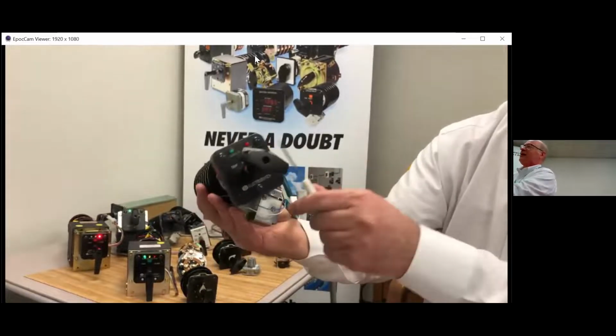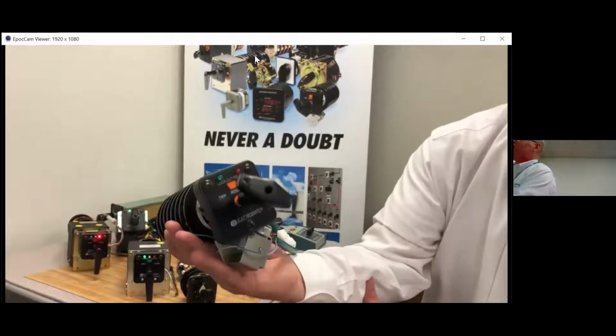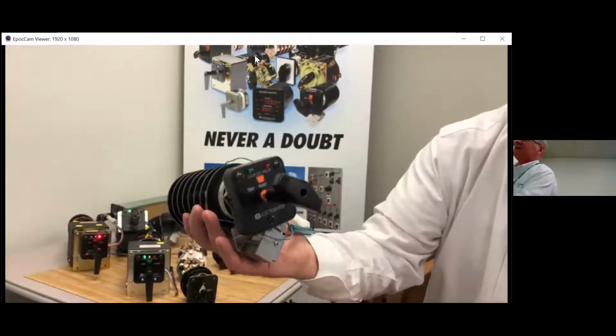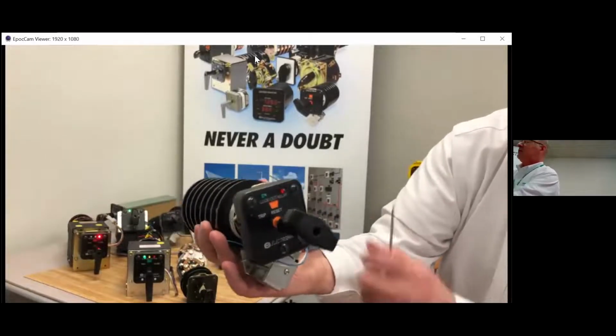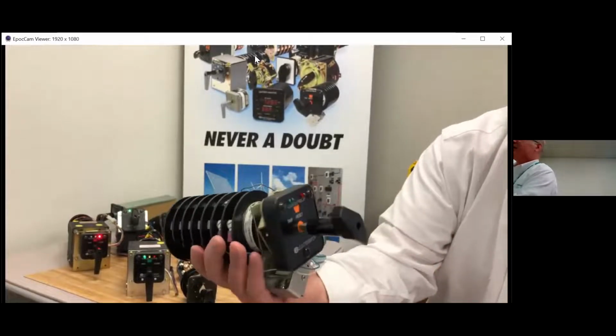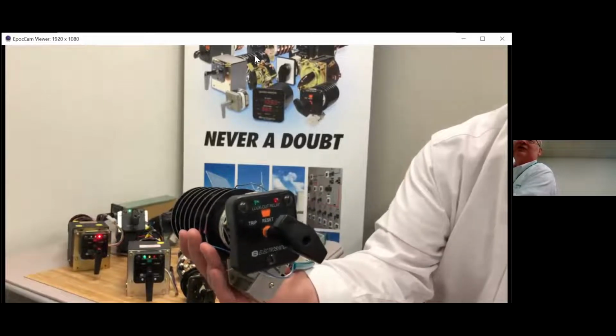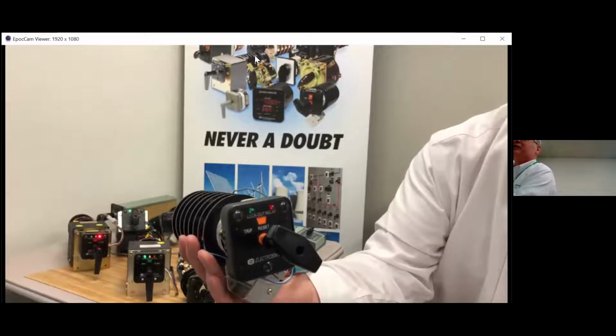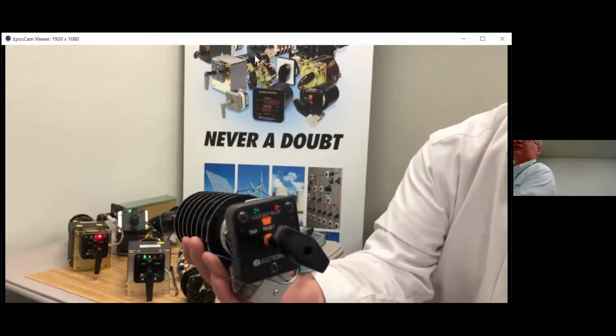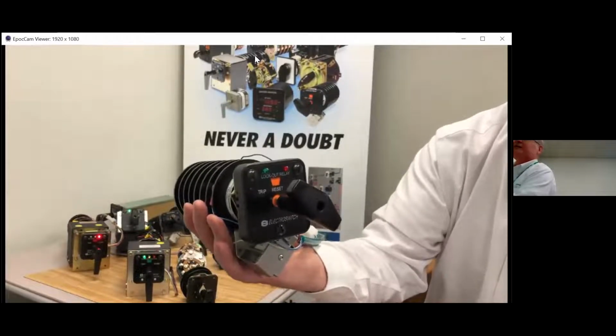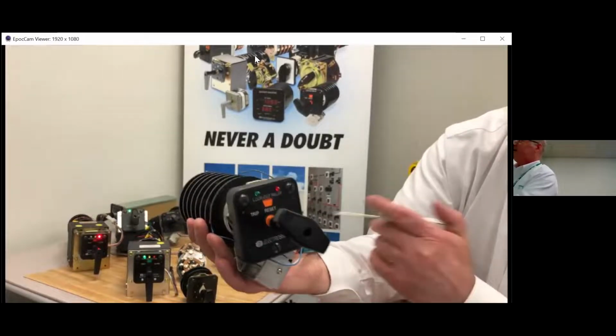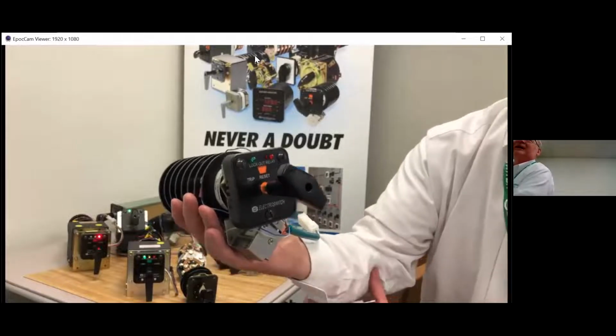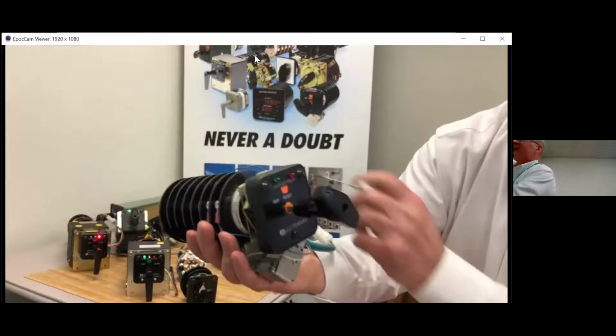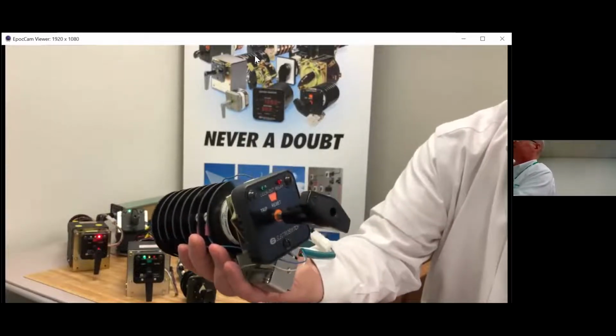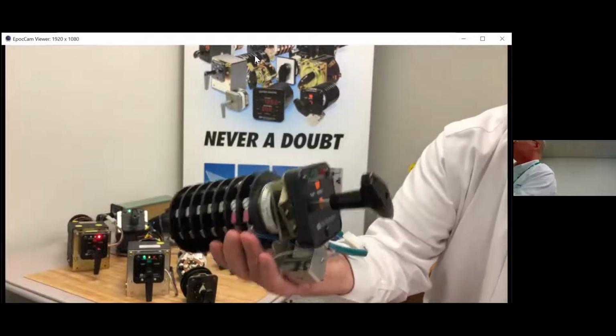And over the years, we've developed a Molex connector that connects the lighted nameplate with the controls of the lockout relay. So if you have any problems with a replacement nameplate and the LEDs, you can remove that without having to pre-test and recommission this relay. In most system protection applications in the field, when you initially install a system like this, your system protection folks come in there and do a commissioning of every termination and how everything is wired. So this is a nice, convenient way to retest and repair and replace the nameplates and not have to rewire the whole switch and retest the whole switch with that connector. So let me do this electrically and show you how that works.